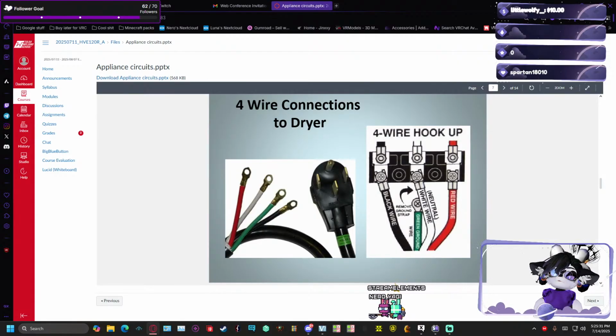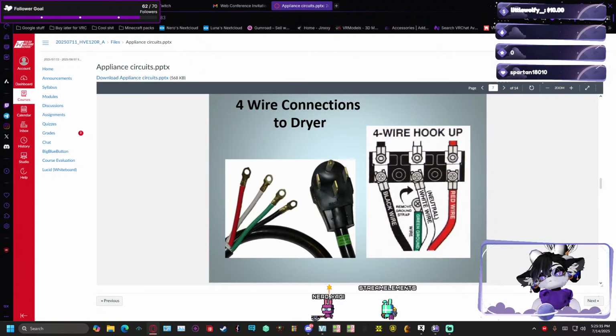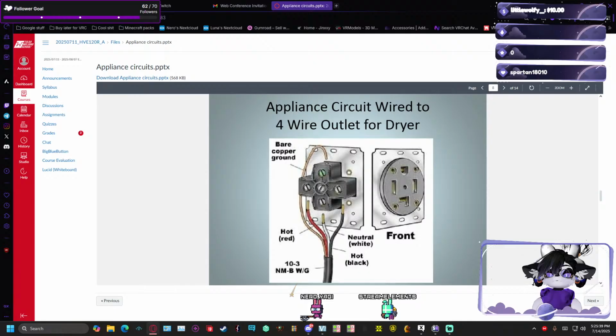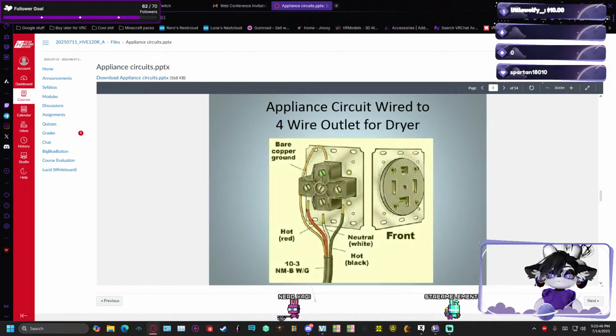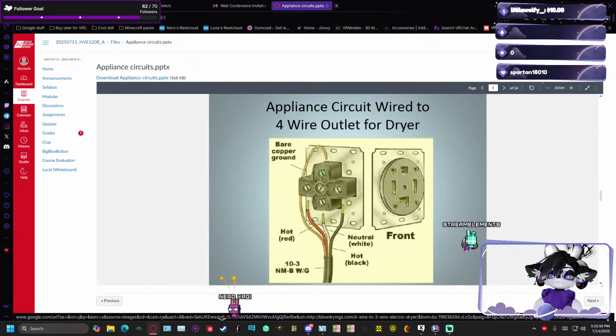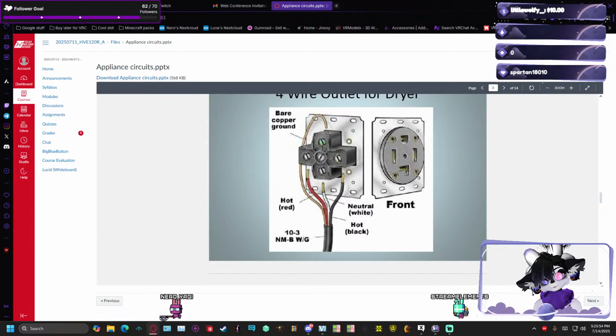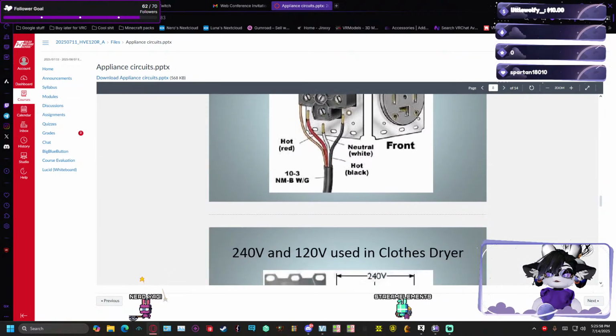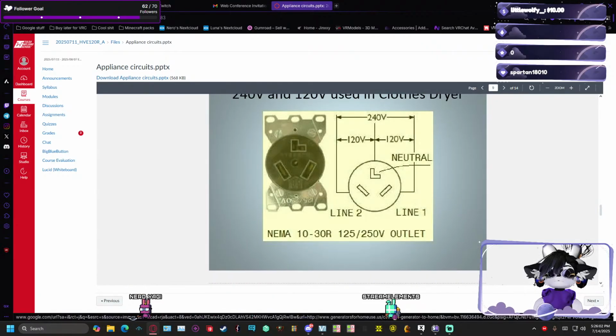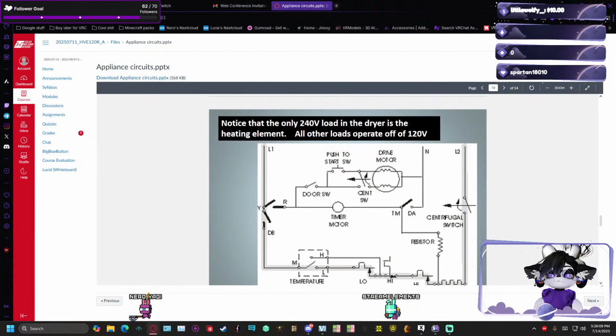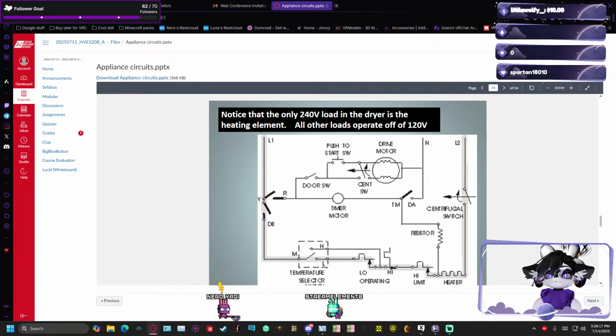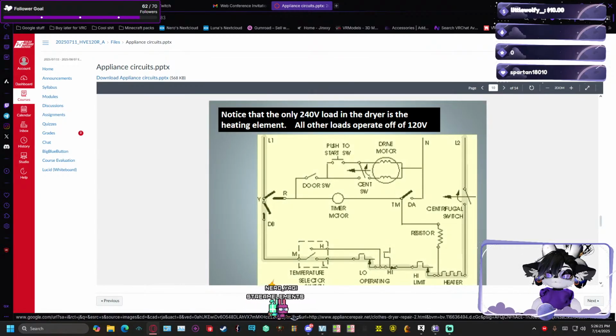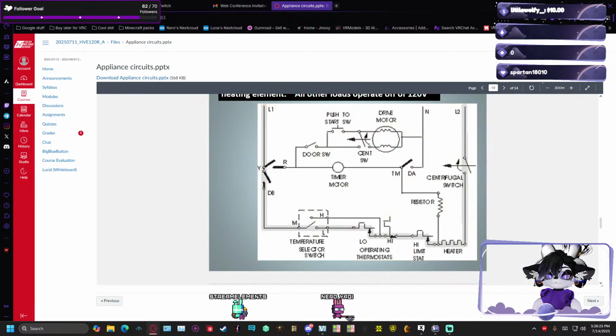Of course, ground, two hot wires and the neutral wire. Wiring for a four-wire outlet for a dryer: neutral goes in the front. Both hot wires go on the side, and the ground goes all the way to the top. Neutral and hot. Notice that the only 240V load in a dryer is the heating element. All other loads operate off of 120. Heater.